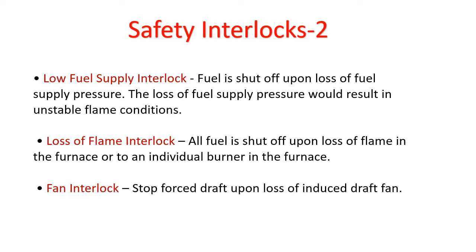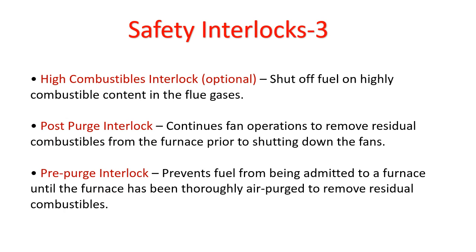Stop the forced draft fan upon the loss of the induced draft fan. So if the induced draft fan is itself not working, then the forced draft fan should stop. Then the high combustible interlock, which is optional: shut off the fuel on high combustible content of the flue gases.